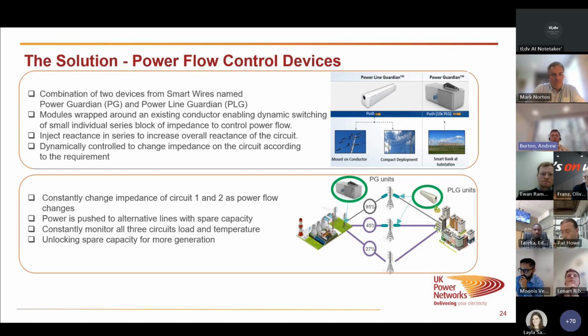So we looked at combining the power guardians and the power line guardians. The power line guardians have lower capacity ability, whereas the power guardians are 10 times more than the power line guardians. These work by being wrapped around the conductors, inducing impedance on the line so you can control power flow, but more dynamically, up to the total number of deployments you've got.